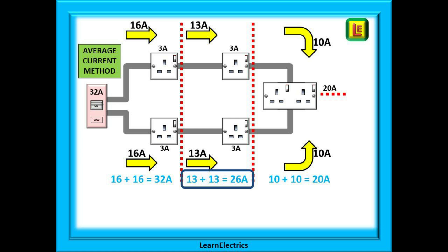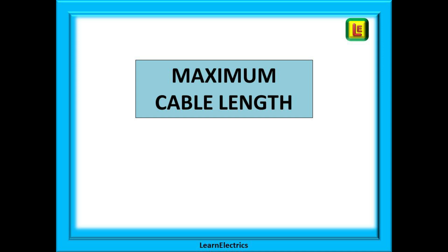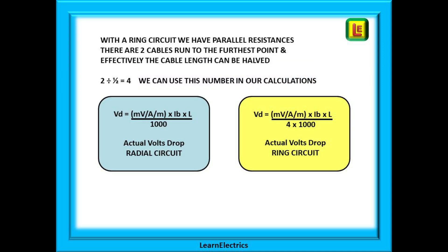Let's start by calculating some maximum cable lengths. If we do this first it is much easier to understand the voltage drop calculation. With a ring circuit we have parallel resistances. There are two cables that run to the furthest point, which means that effectively the cable length can be halved. Two cables, half the length. Two divided by a half gives us four. Now remember this number four, we're going to use it in our calculations.